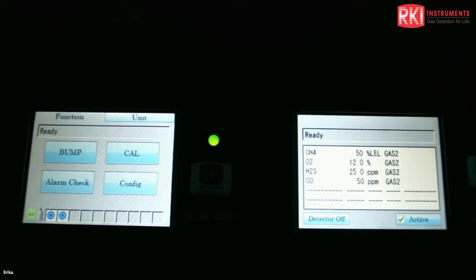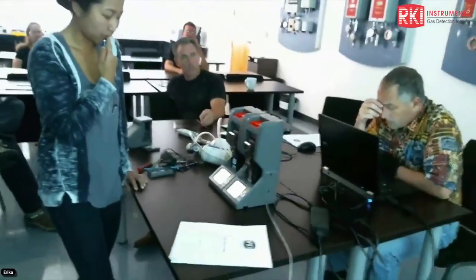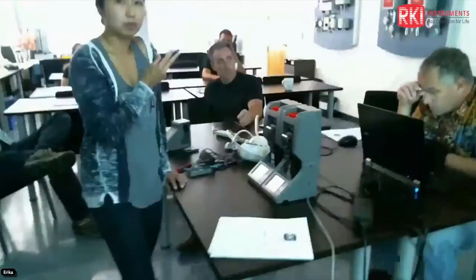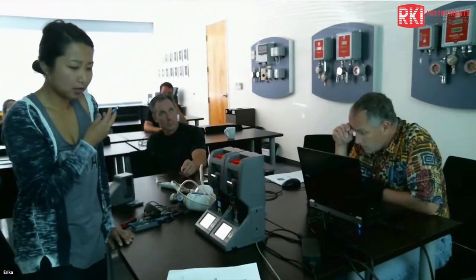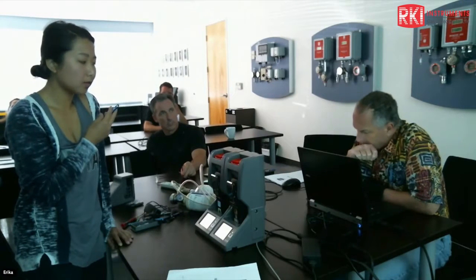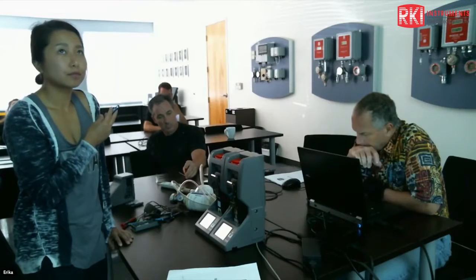Okay. So mine is coming up saying inlet error. It's passed on all the calibration. I mean, all the bump tests passed, except for the HCN. It's got dashes, dashes, dashes, and no information. In the 6000 instrument, I have it set up to calibrate only 4 gases because I do not have HCN gas. Oh, so you don't have HCN gas, you said? I do not have HCN gas, so in the 6000 I have the calibration procedure for 4 gases only, so it will reset the date when I calibrate.